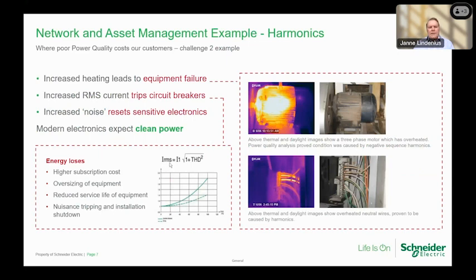This is a network and asset management example of the harmonics. What harmonics do is heat up the equipment, leading to premature failure and costing you increased OPEX money. Harmonics also increase currents in the circuits, leading to trips in the breakers and causing you unnecessary process stops. Harmonics are also a source of noise for sensitive equipment, which may react to noise, giving you false information or production shutdowns. What you see here are 2 examples of the cause and effect. We will come back to these examples later on in this webinar.